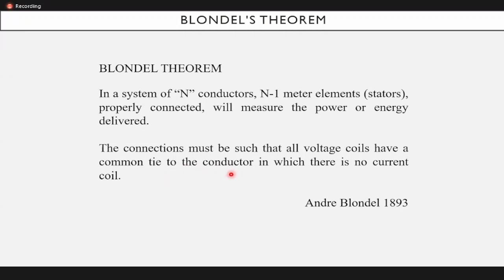For a polyphase system, if energy is supplied to any system of conductors through N wires, the total power in the system is given by the algebraic sum of the readings of N watt meters, so arranged that each of the N wires contains one current coil, the corresponding voltage coil being connected between that wire and some common point. If this common point is on one of the N wires, the measurement may be made by the use of N minus 1 watt meters.